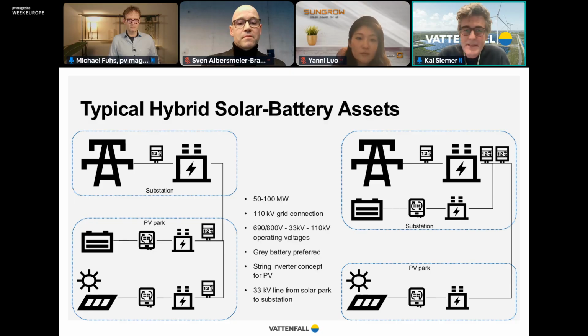The main choice we have is putting the BESS either inside the solar park or in the vicinity of the substations. The vast majority of our systems is connected to the high voltage line, typically 110 kV, and then we can put the BESS either near this point of interconnection or in the park.